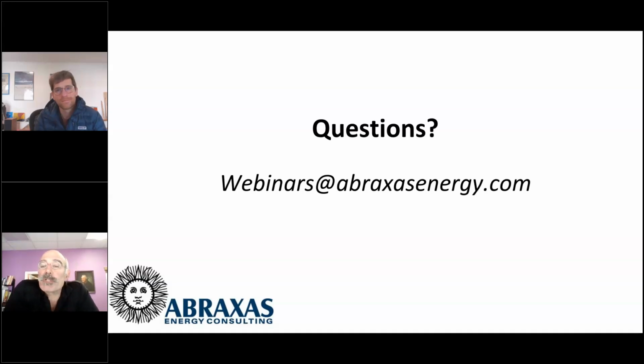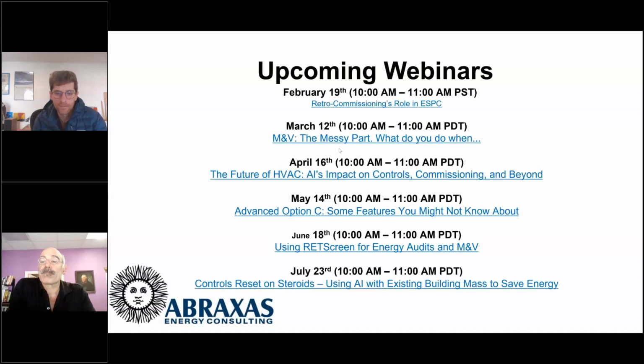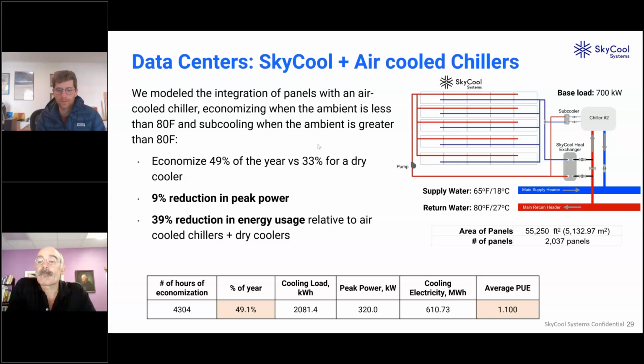So okay, we work on chilled water with cooling towers and flat plate heat exchangers in winter. Yes, exactly. And so that's really what we're doing here to get this economizing. This is a data center example, but it would be true of any type of system, as long as the supply water temperature is warmer than what we can provide, then we should be able to add essentially capacity to the chilled water system. Okay. That makes sense. Yeah.